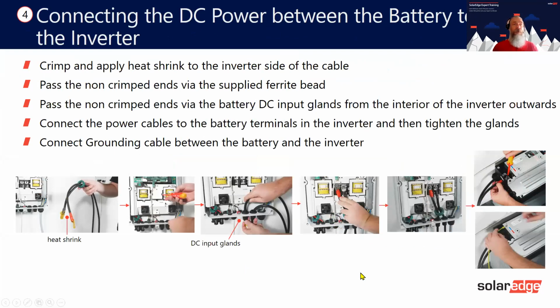The DC cables, this is a very good tip. You want to put the crimp lug on the end. Then you want to put your heat shrink on there, about 150 mil of heat shrink. And then when you've done that, it's easier to pass them through a ferrite coil and then through the gland this way, rather than trying to pull them up and then trying to crimp them. So we found here that it's a lot easier to do it this way. So you prepare it like here, and then you pass the ends through. That's the easiest way. And then you connect them to the battery here, plus and minus, just into a normal screw terminal.